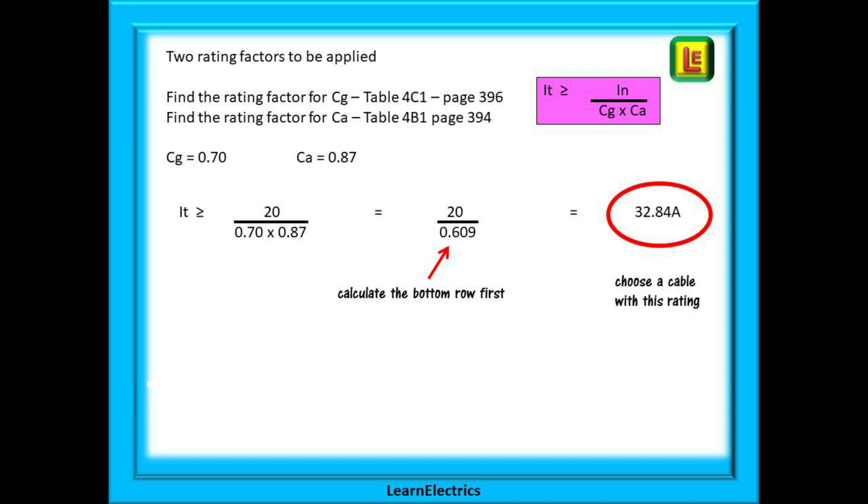Look on page 373. Find the rating factor for CG table 4C1 on page 396 which is 0.70. Find the rating factor for CA table 4B1 page 394 and this is 0.87. And work these two out first. Multiply 0.70 by 0.87 and we have a new number 0.609 for the bottom row. Now divide the breaker size 20 amps by 0.609 to give us 32.84 amps. The cable we should choose must be able to take 32.84 amps or more in normal conditions.